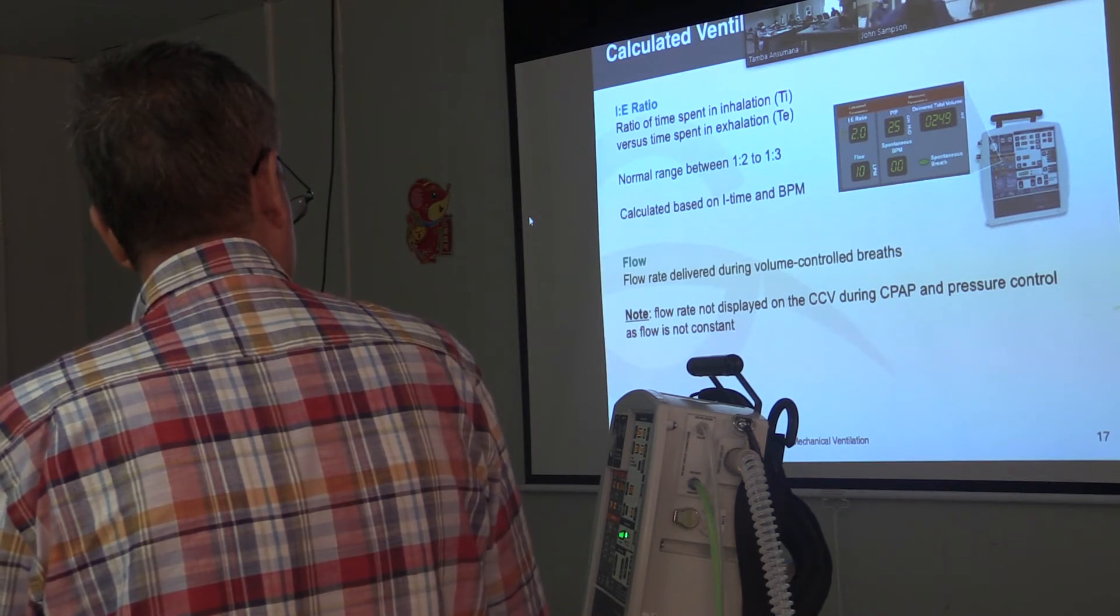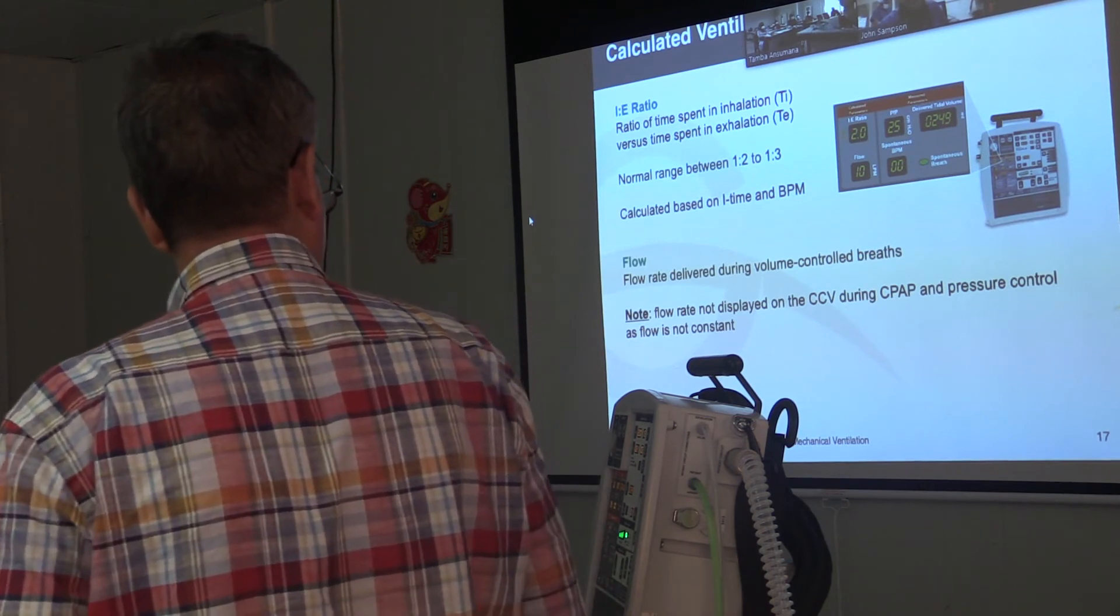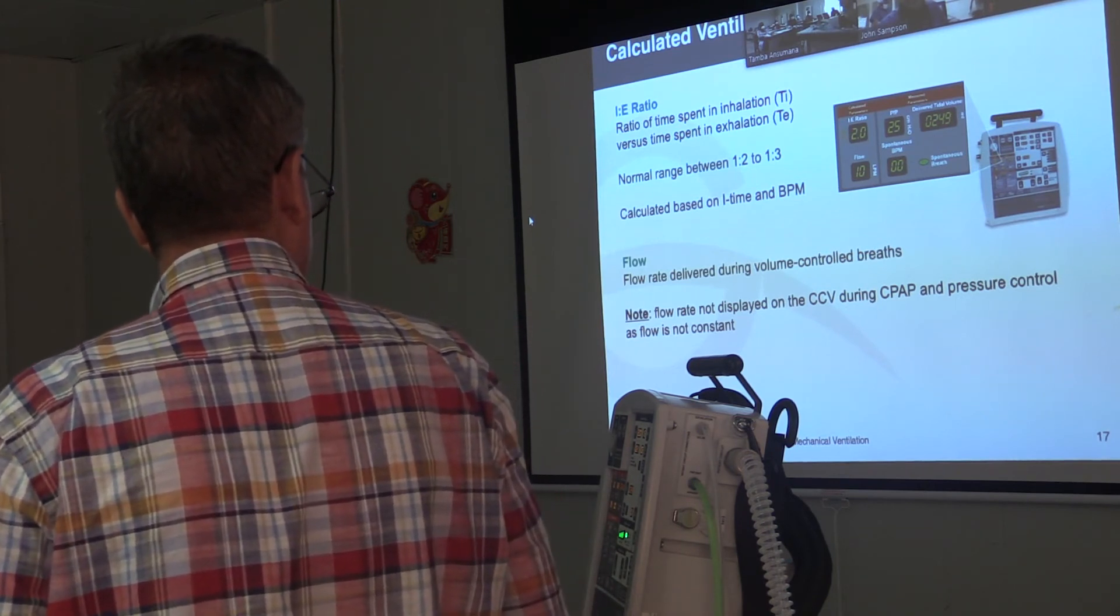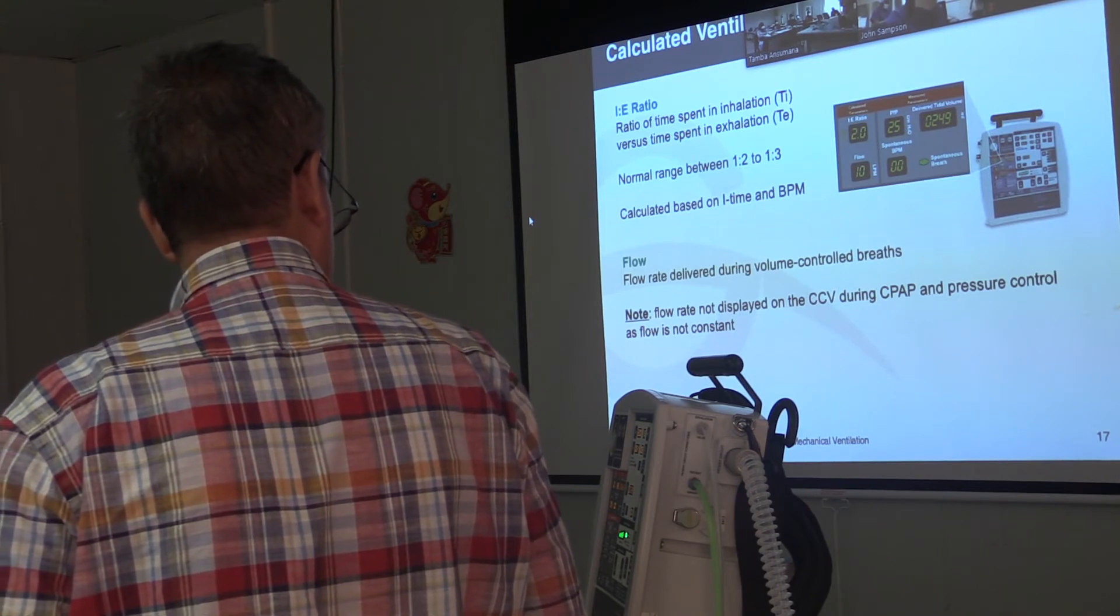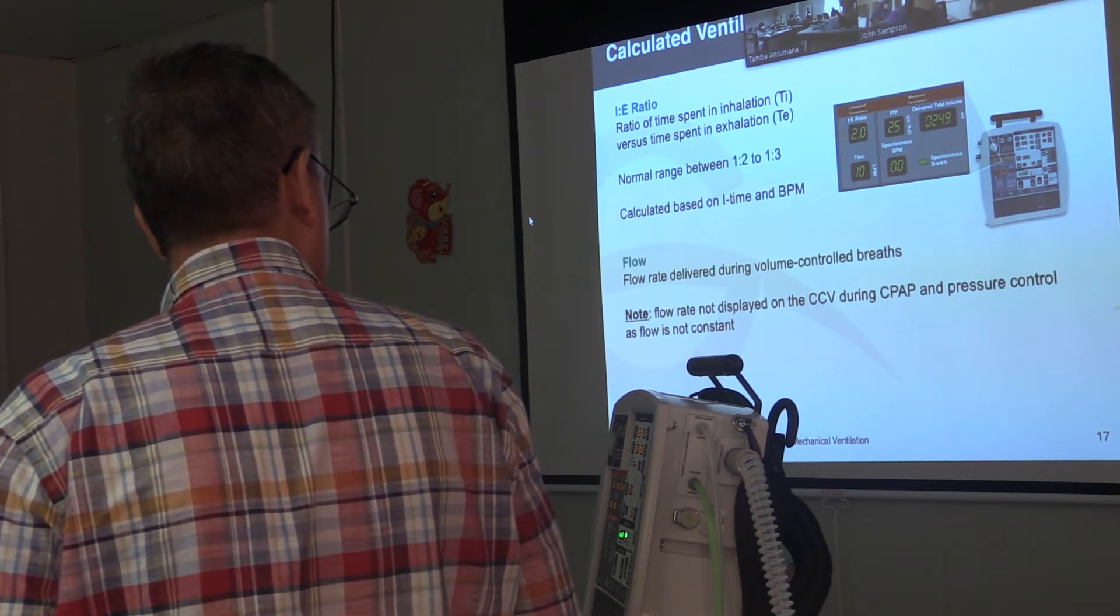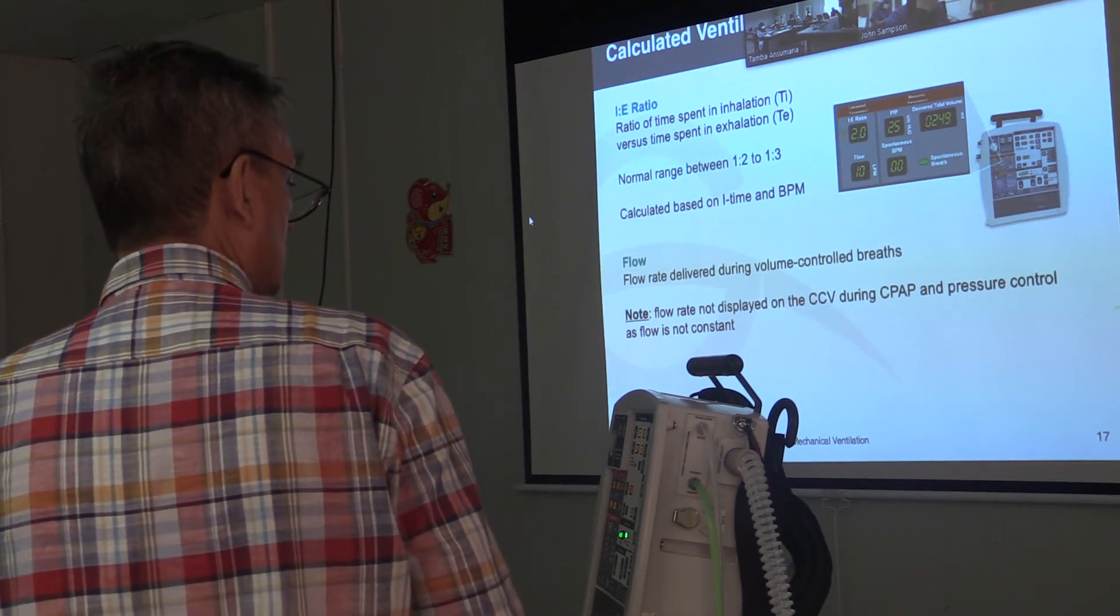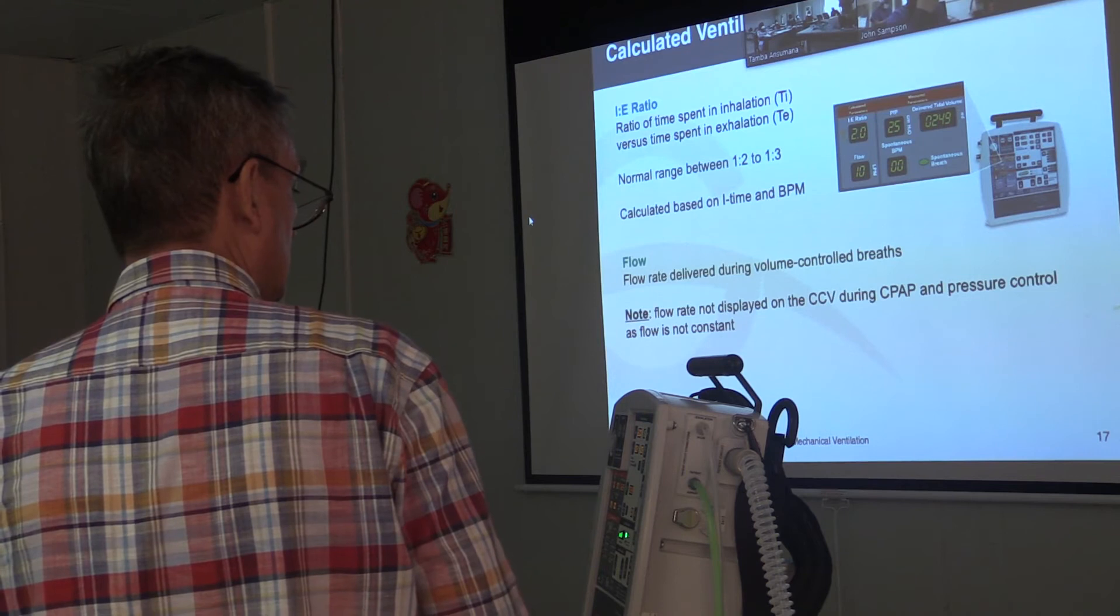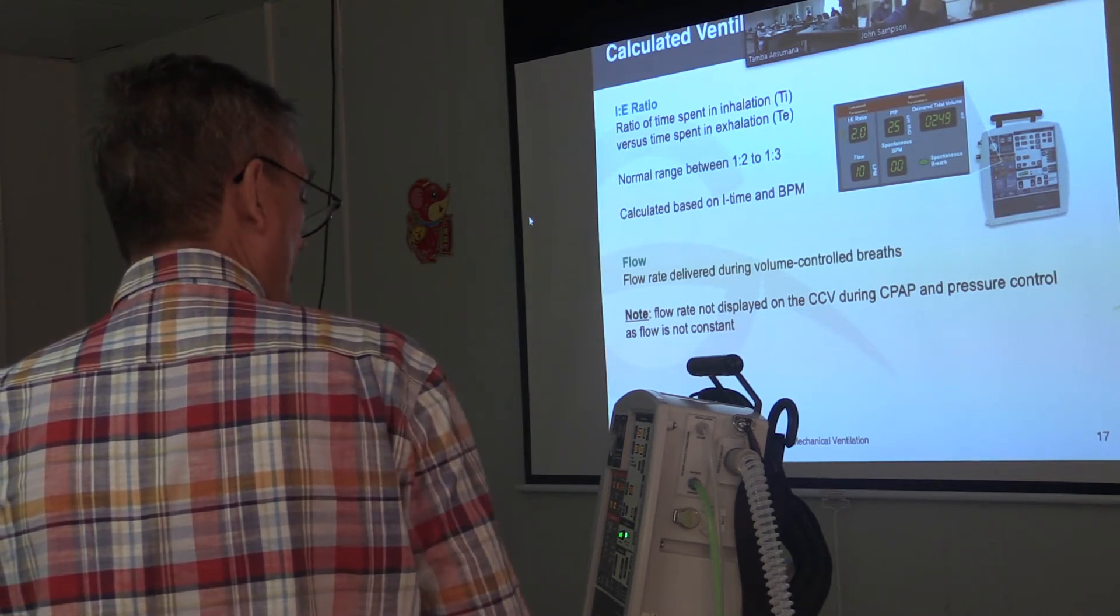Just one small note here is that the flow rate is not shown during pressure control breaths. That's just because the way that the ventilator delivers those breaths, it starts at a high flow, and then slowly decreases the flow as you get closer to the target PIP. So it's not calculated, and so it's not shown. So if you don't see it when you're ventilating in pressure control modes, that's okay, and that's why.